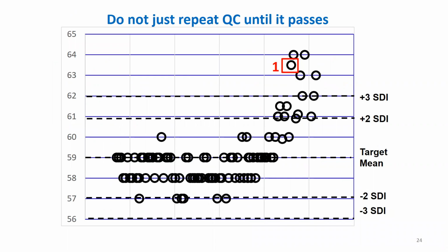It is important to note that technologists should not just keep repeating QC until it passes. So in this case, after repeating with fresh QC, a repeat failed. Sometimes the technologist will just try another repeat. In this case, the repeat would have passed.